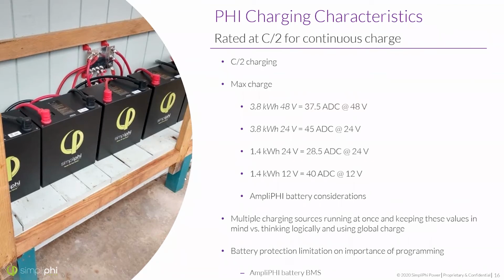So that is the 37.5 amps DC per battery, the max you can charge per battery. If you've got a bank of 3, multiply that number by 3. 24 volt, 45 amps DC is currently how much? That will be changing here shortly, I believe, but that is a little bit less than C/2, so keep that in mind. So the 24 volts are definitely designed not to be used as strongly as the 48 volts.